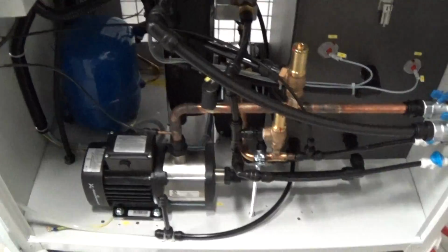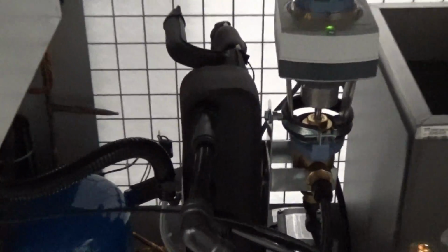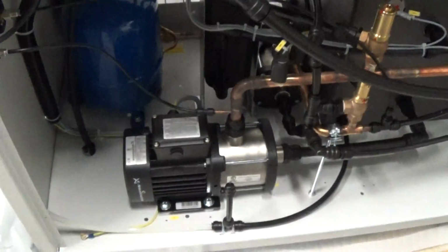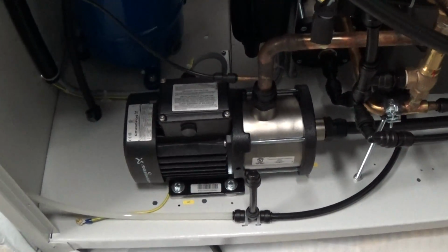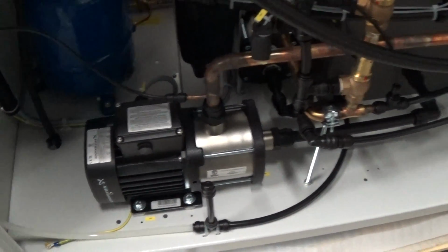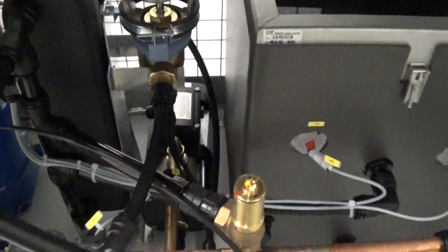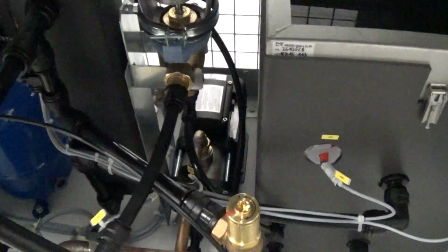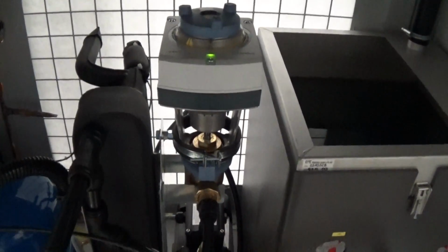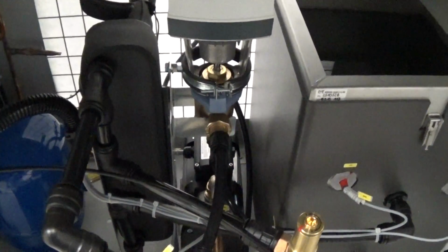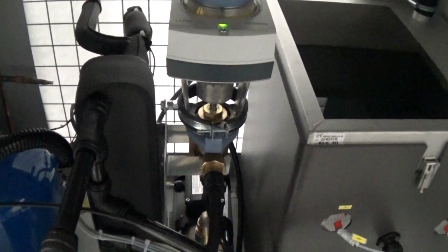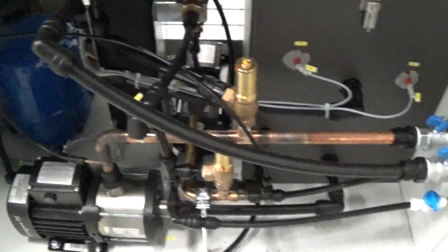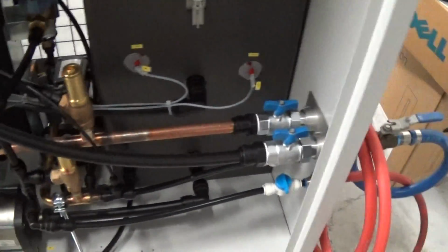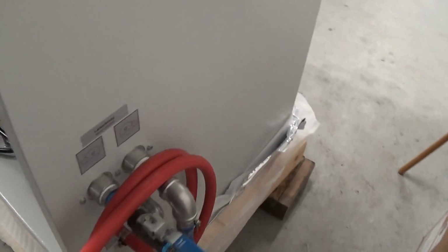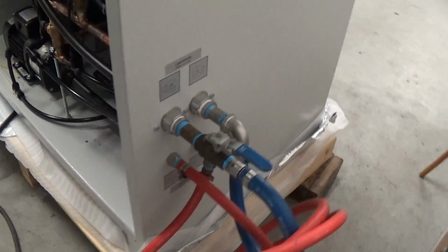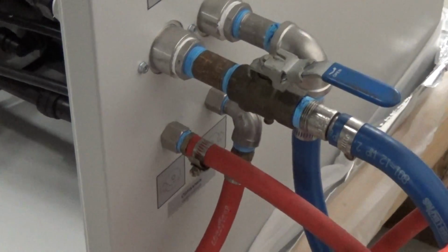So what that means is the unit does just have one brazed plate heat exchanger. It has one primary process pump. That's the one we'll be using. But it also has a secondary smaller pump there, a modulating or 3-position valve, and what they did is they would steal a little bit of the process water from the primary flow for this secondary circuit. That secondary circuit is simply those smaller fittings you see right there.